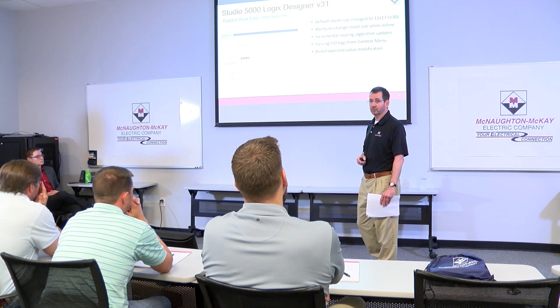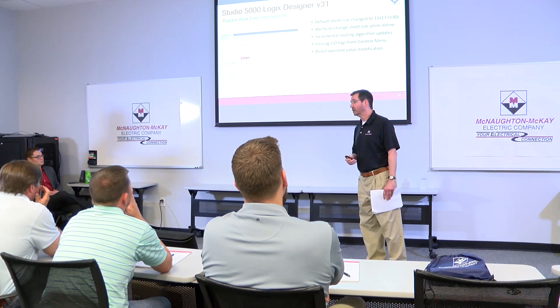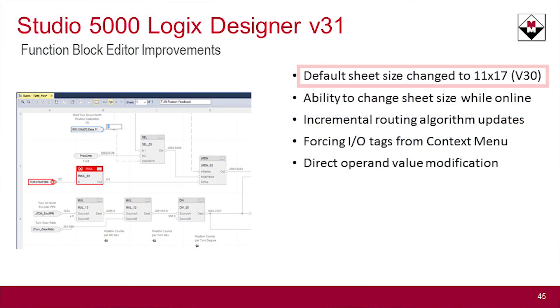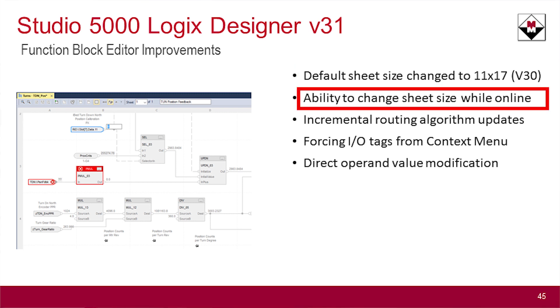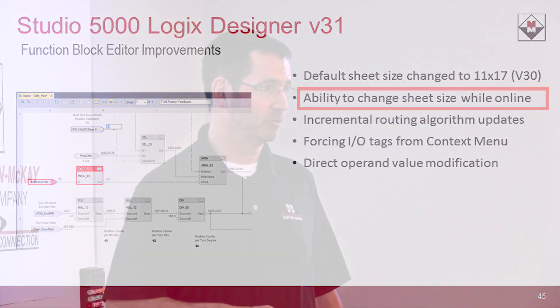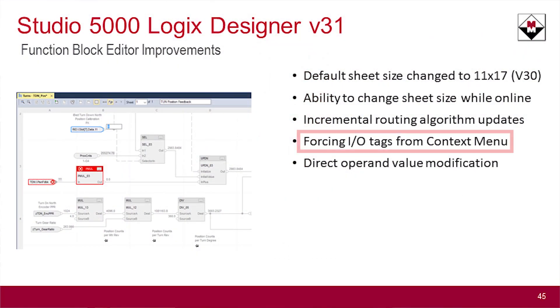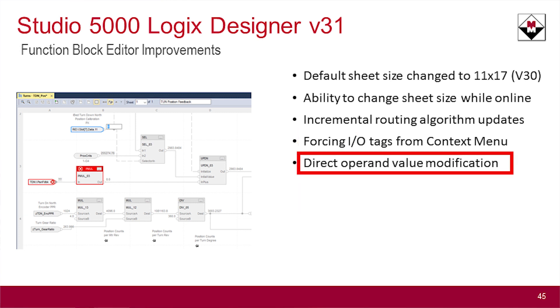The function block editor also has several improvements. The default screen has been changed to 11 by 17, and they're allowing you to change the screen size online as well. Previously you had to take it offline to change it, but now you can do that online. You can also force IO tags directly from the sheets, as well as change operands directly there.